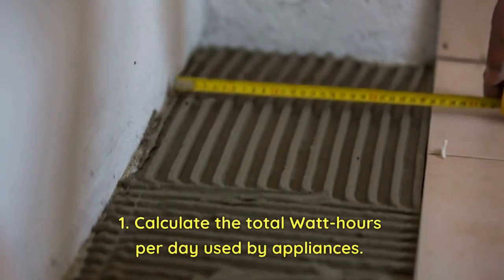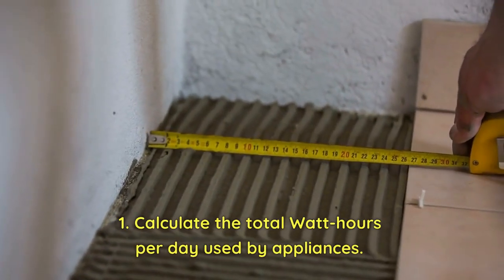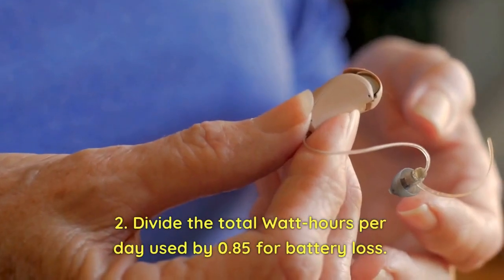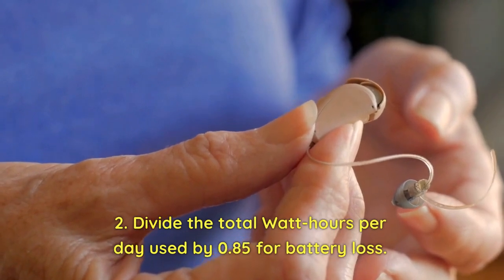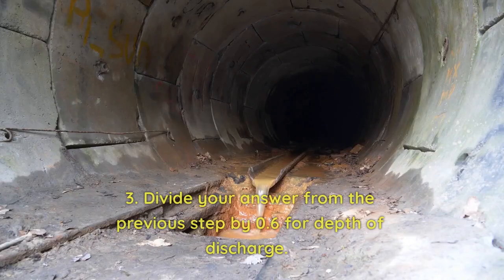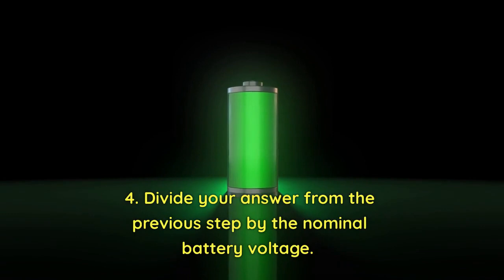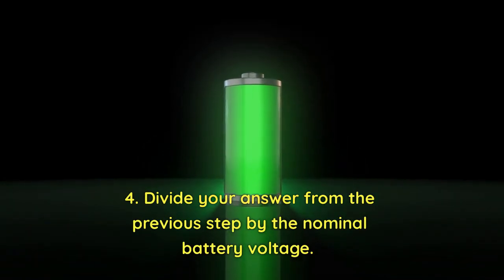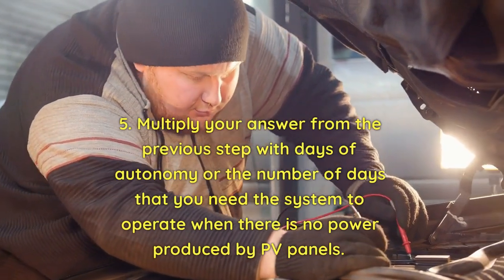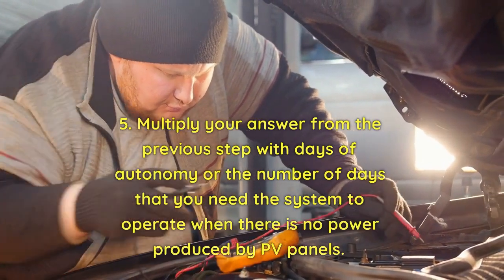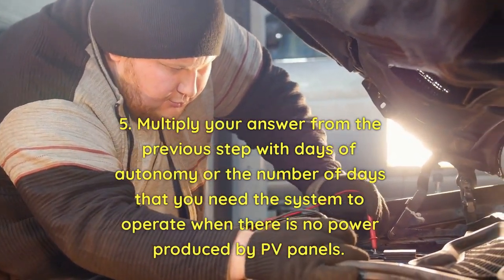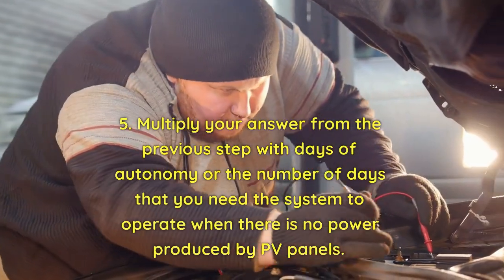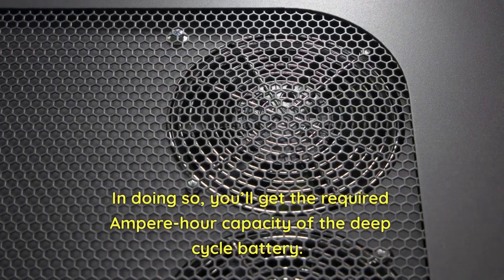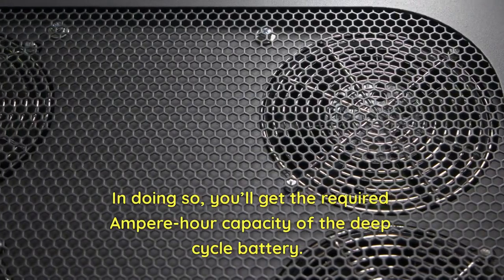1. Calculate the total watt-hours per day used by appliances. 2. Divide the total watt-hours per day used by 0.85 for battery loss. 3. Divide your answer from the previous step by 0.6 for depth of discharge. 4. Divide your answer from the previous step by the nominal battery voltage. 5. Multiply your answer from the previous step with days of autonomy, or the number of days that you need the system to operate when there is no power produced by PV panels. In doing so, you'll get the required ampere-hour capacity of the deep cycle battery.